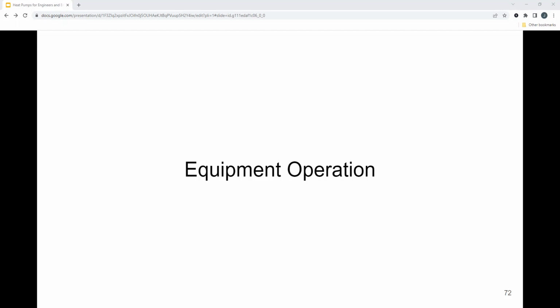All right, so I'm just going to answer one question that Jim asked. Why are heat pumps not a good application for Home Depots? Similarly, buildings with high air change requirements. So what I was getting at with the Home Depot is, the ceilings are 30 feet plus, and with VRF equipment, there's not a whole lot of options on the fan coil side. Typically with something like that, you would install a concealed ducted unit. Max you can go is about 8 tons on that. And as we start talking about how large a volume a Home Depot or a box store is, typically with something like that, we're not going to have great stratification. And for the amount of air that's needed, you're going to be sizing large tonnages for VRF equipment.